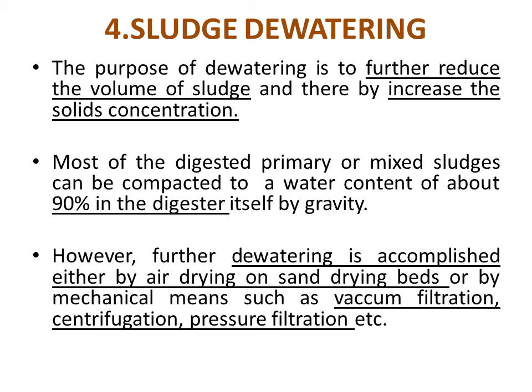The fourth process is sludge de-watering. The purpose of de-watering is to reduce the volume of sludge and increase the solid concentration. Sludge normally contains 95 to 98 percent moisture. We must remove that water content to reduce volume and easily dispose of the sludge. Most digested primary or mixed sludge can be compacted to a water content of about 90% within the digester itself by gravity.